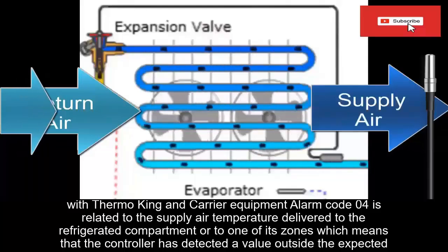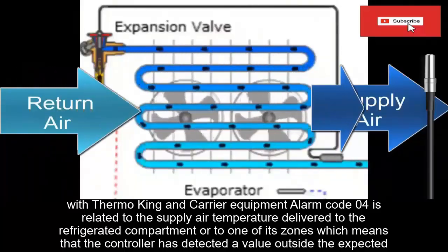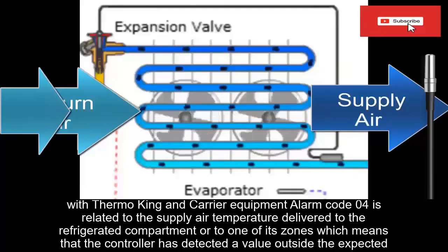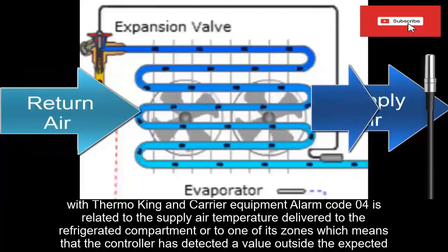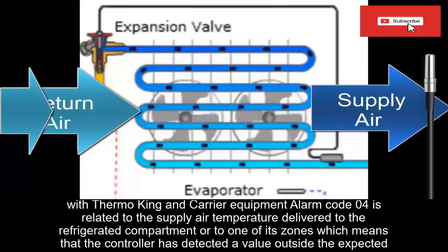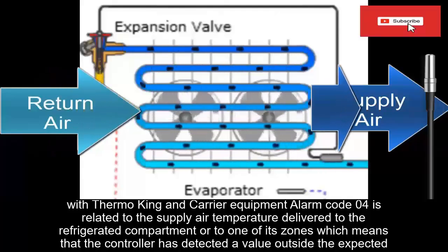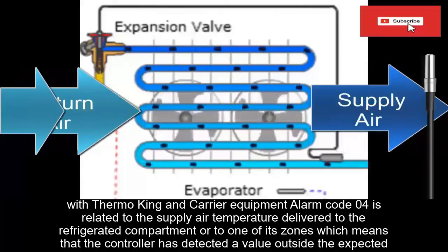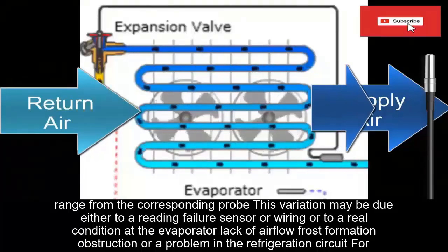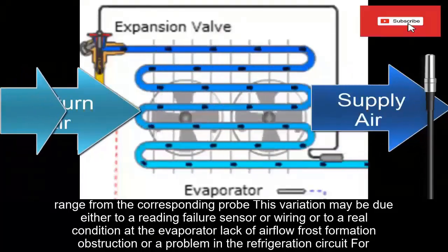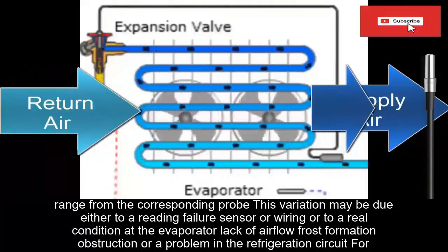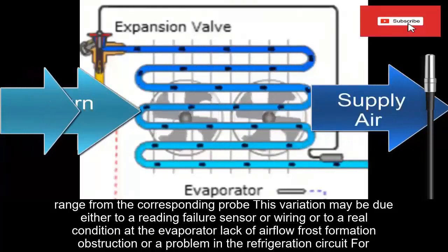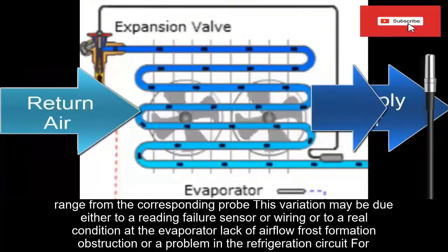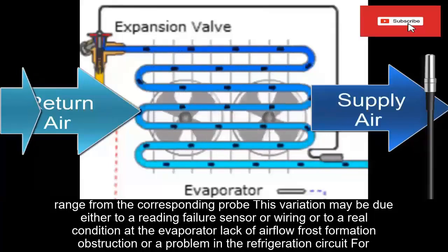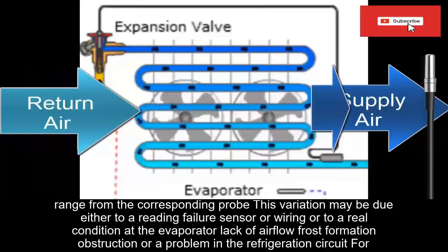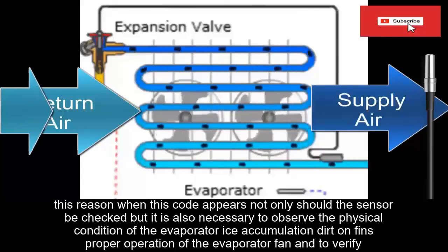Alarm Code 04 is related to the supply air temperature delivered to the refrigerated compartment or to one of its zones, which means that the controller has detected a value outside the expected range from the corresponding probe. This variation may be due either to a reading failure, sensor or wiring, or to a real condition at the evaporator, lack of airflow, frost formation, obstruction, or a problem in the refrigeration circuit.